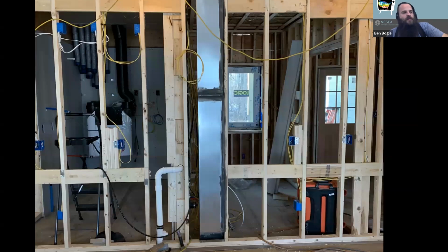What that does is cause something Ross touched on, which is entrainment. This air flows out of the 3¼ by 10 duct right underneath the range, spills up around the range from the bottom, and creates a negative pressure situation as it passes the cooking surface, pulling all that exterior air up and into the flow path of the hood on its way up.